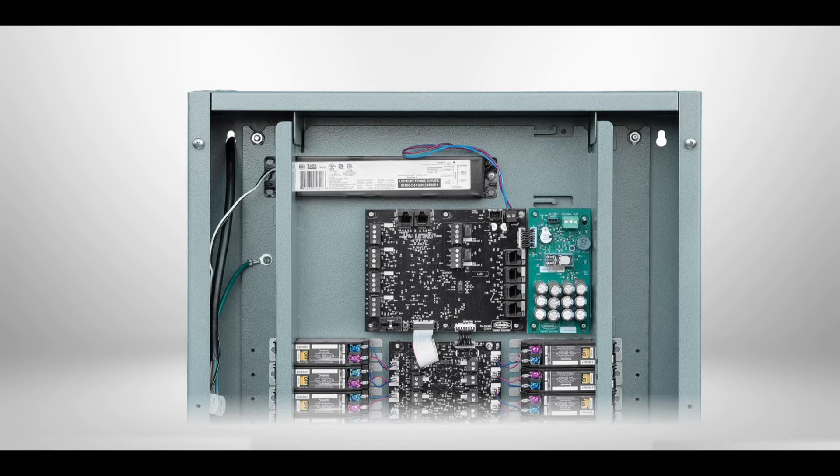Each input can be individually programmed. The NX panel also features two SPDT, or normally open/normally closed, dry contact outputs. Connect the contact closure output to the output terminal headers using 18 gauge wire. Each output has a contact rating of 24 volts DC at 50 milliamps maximum.